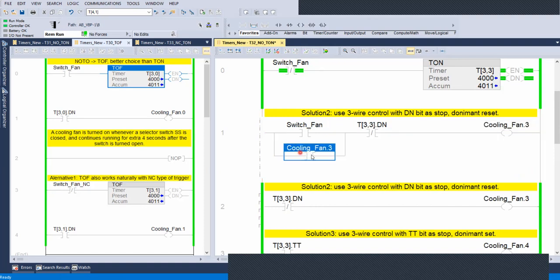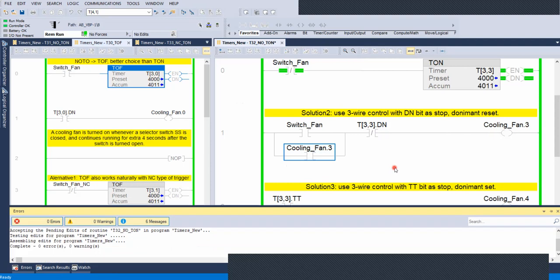Once the output turns on, we want to keep having the continue path until the stop condition is met, right? We start from here, stop at here, but the start will turn off before the stop eventually turns off. So that's why we need to bypass it, right? Typical 3-wire control logic, right? So we finalize this, then let's look at here.